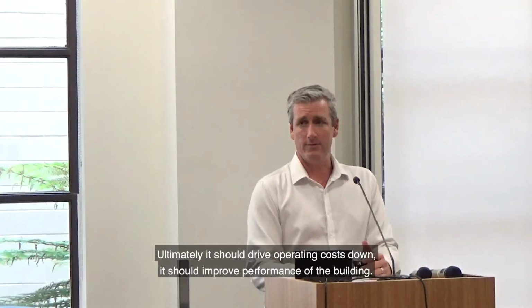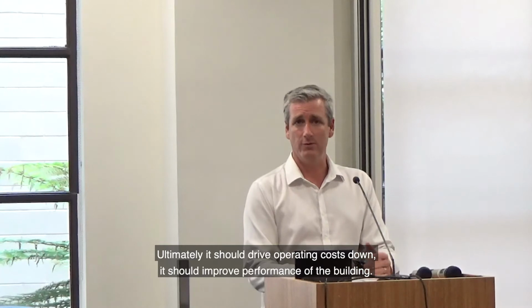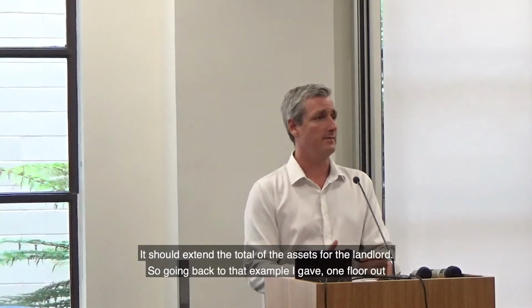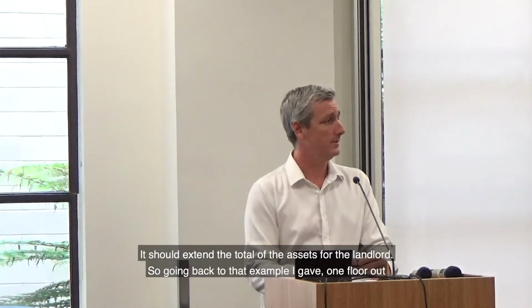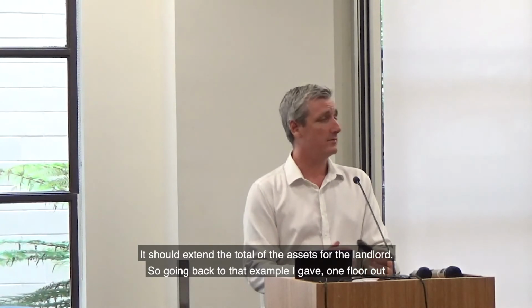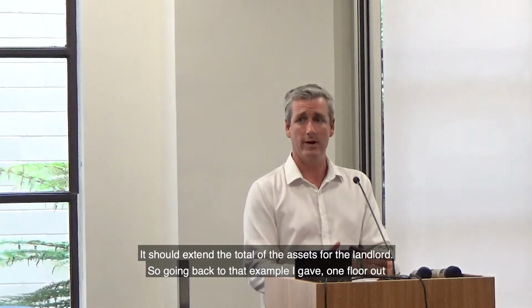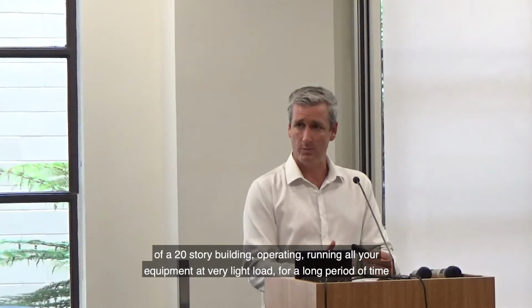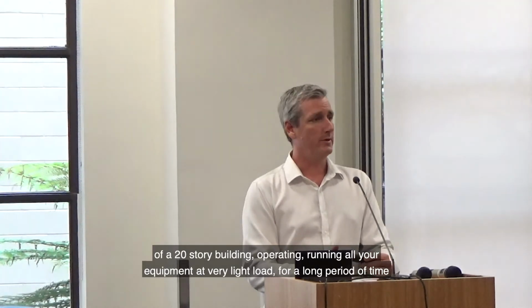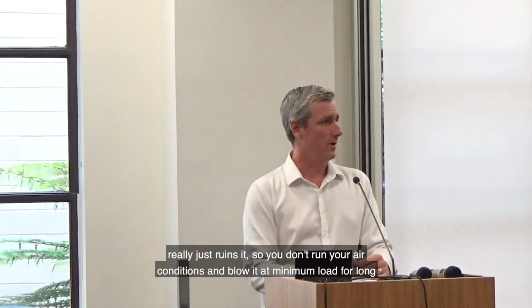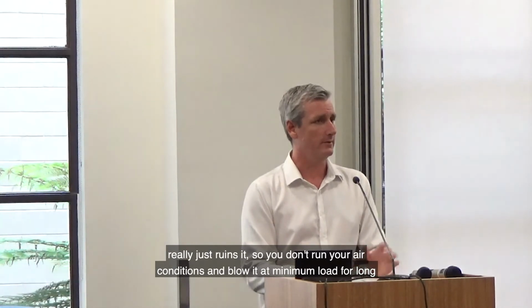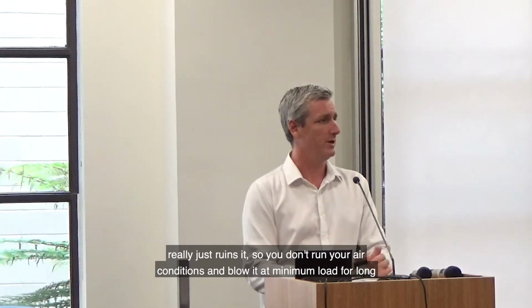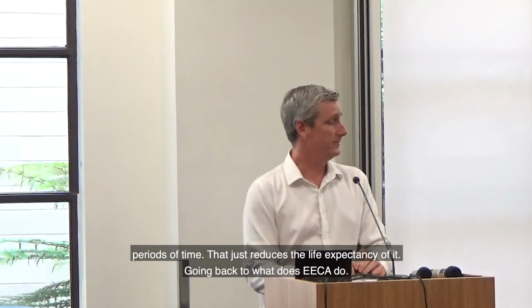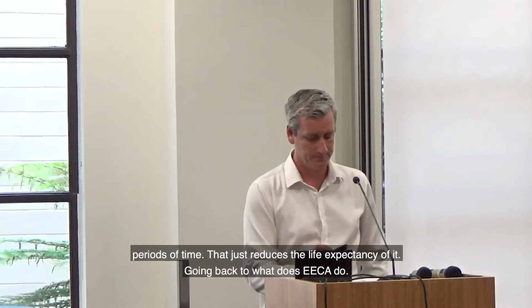Ultimately, it should drive operating costs down. It should improve performance of the building. It should extend the life of the assets for the landlord. Going back to the example I gave, of 1 floor out of a 20-story building running all your equipment at very light load for a long period of time really just ruins it. You don't want to run your air conditioning and boiler at minimum load for long periods of time, it just reduces the life expectancy of it.